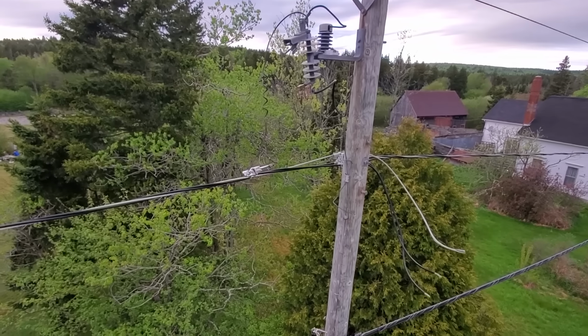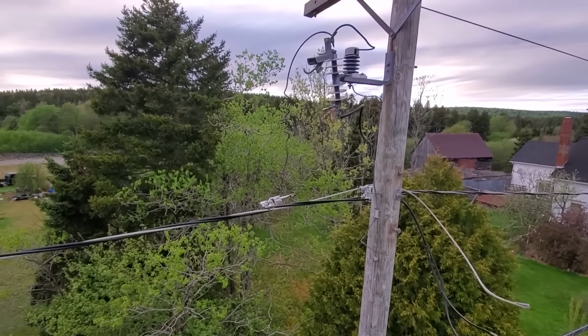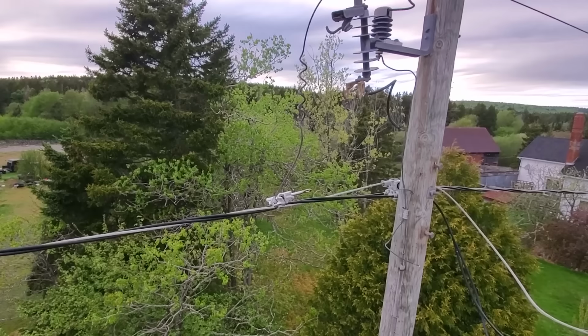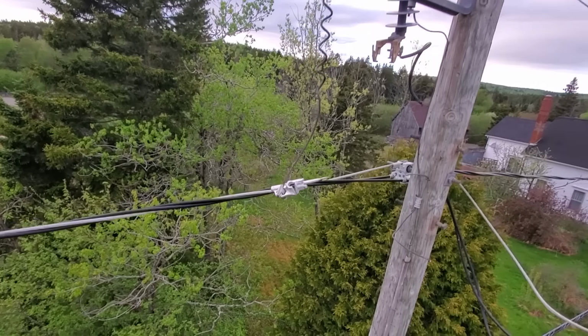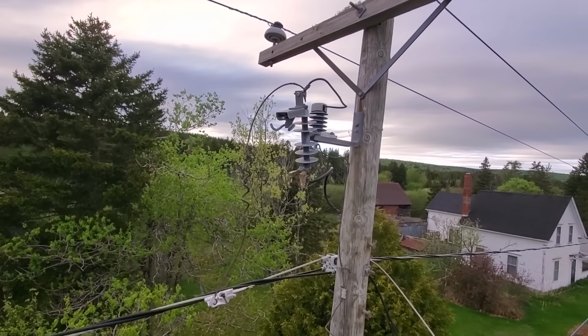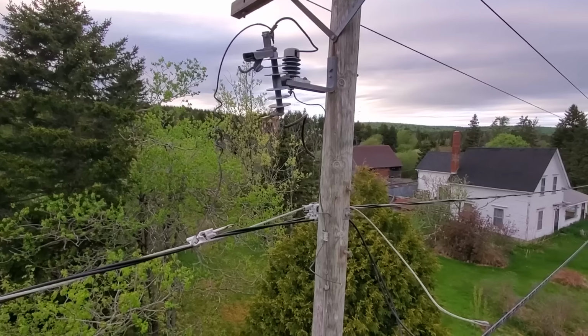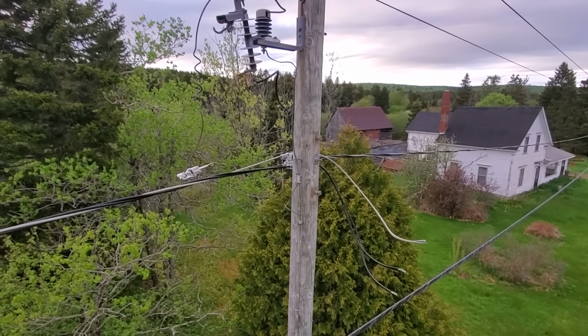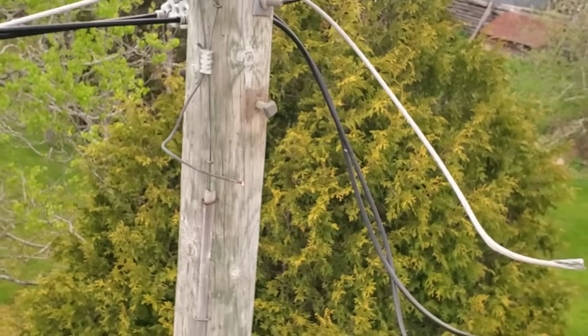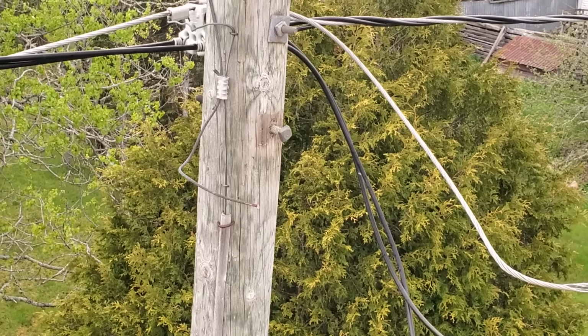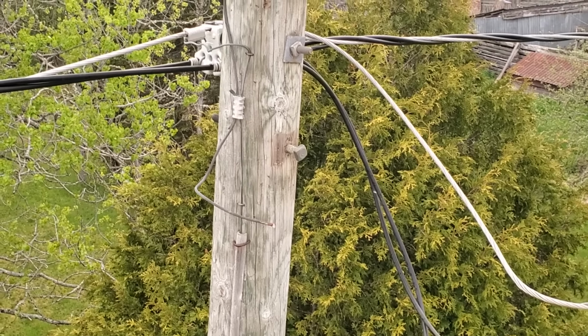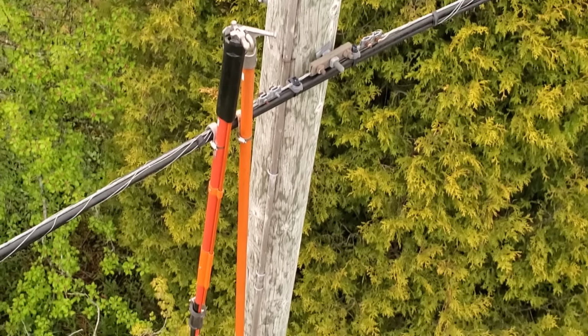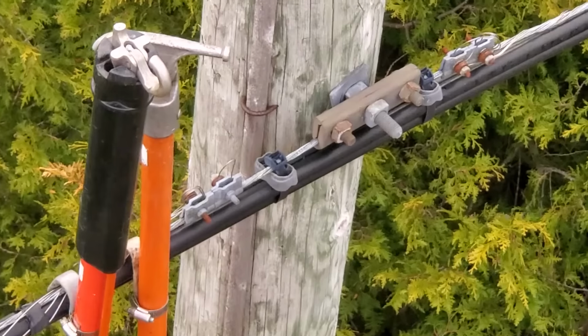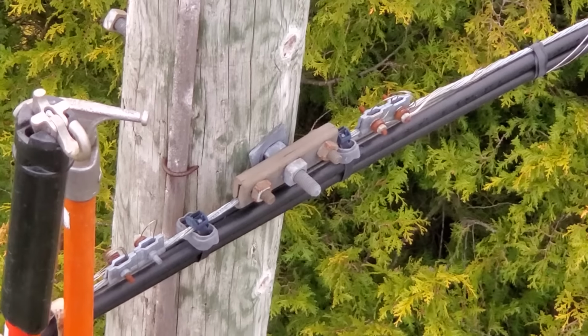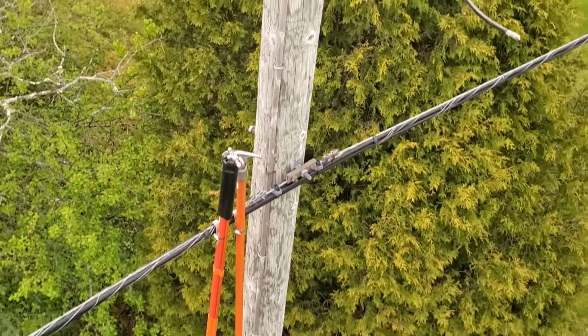Also a good idea to check your cutout and your tap clamp and connections and stuff, but that one's almost brand new, newer style polymer cutout. You won't have to change out any of that equipment. That copper lead right there is the case ground that bonds the case of the transformer to the neutral, as well as to our butt ground, which runs down the pole. Every fifth span or so is bonded to the telephone, so this span of telephone is not bonded.